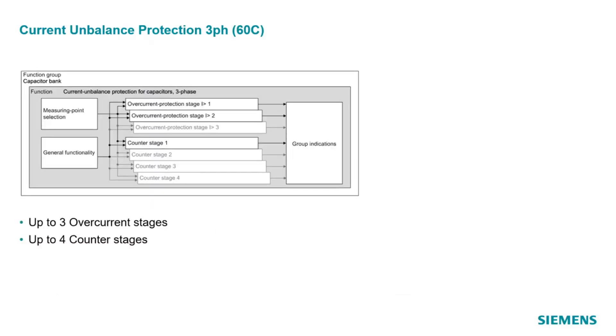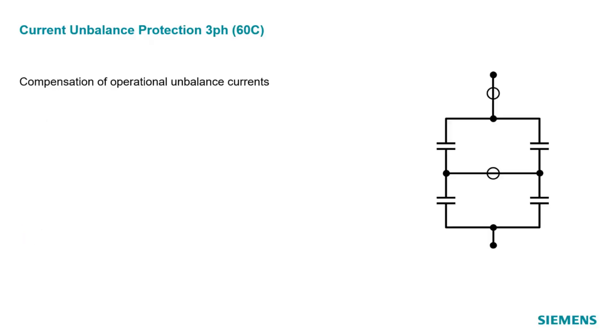The current unbalanced function has two types of stages. First, an overcurrent stage — a maximum of three stages are available of this type. Second, a stage for counting defective capacitor elements — up to four stages are available. Even without defective capacitor elements, the cap bank can show operational unbalanced currents. They can be caused by manufacturing tolerances, temperature changes, aging, and disturbed detection of defects. To overcome this problem, the function can work with compensated currents.